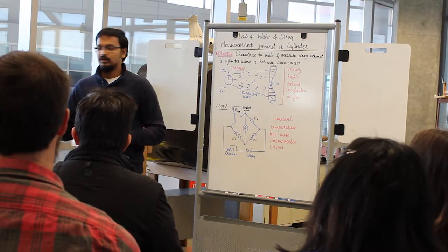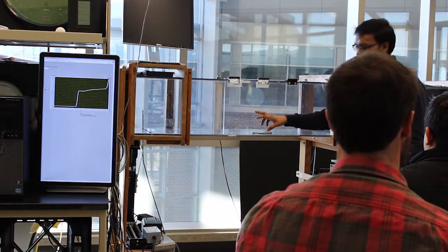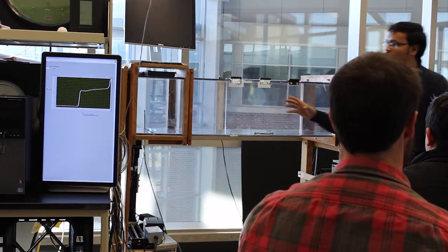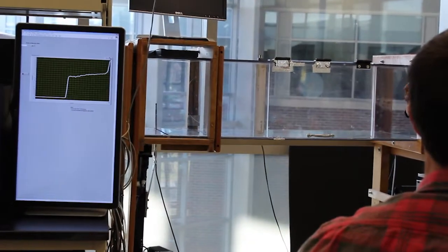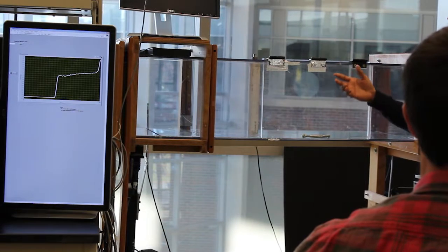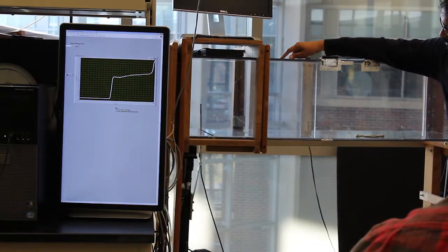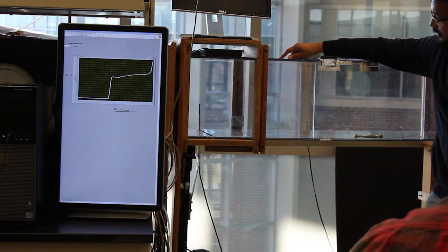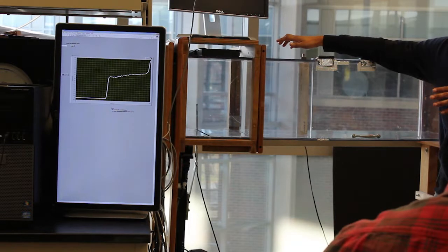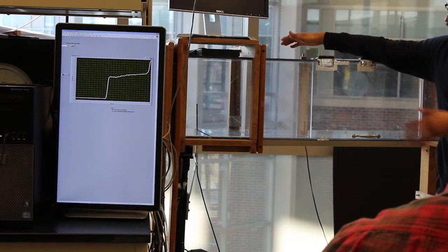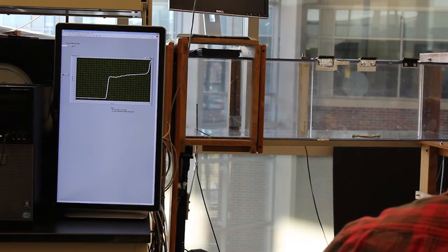So in order to do this experiment, we will first install a cylinder in the wind tunnel as shown here, and you will turn on the tunnel and set it to a velocity that you want to measure this wake structure at. And once you have that, you will use the hot wire probe, which is the probe that you can see at the farthest end of the wind tunnel. And that hot wire probe, when you start the computer program, will traverse from that end to the end closest to you and will stop at intervals of 0.1 inches.